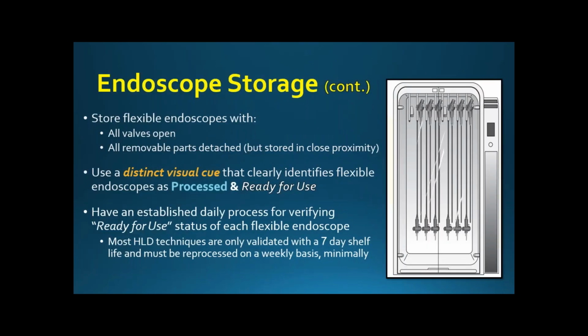You want to make sure that all scopes are stored with their valves open, and that all their buttons and things like that are detached. They have little pockets you can attach to the top of the scope so they can maintain all their buttons. And the other part is that the recommendation now is that a scope should be reprocessed if it hasn't been used for 7 days. So have a process in place so that everybody on staff knows when it's ready to use: this scope has been processed within the last 7 days and it's ready to use. Having a good process in place means there are no errors in that regard.